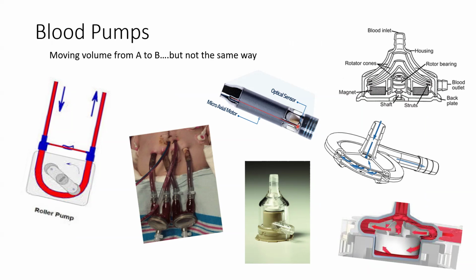That's intracorporeal life support because the pumping mechanism is within the body itself. And then over here on the right, you have three different centrifugal pumps. The top one is the first centrifugal pump to come to market, the BP80 pump head from Medtronic, that had concentric rings that would spin, and shear forces would cause viscous drag to actually push the blood outwards. And then you have the two current workhorses on the market, the Rotaflow and the CentriMag. They're very similar pumps, with the exception of the CentriMag, formerly known as Levitronix, which uses a magnet that lifts the pump body up within the fluid/blood itself.